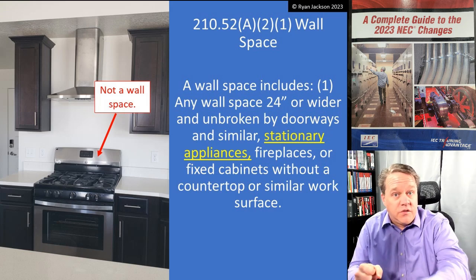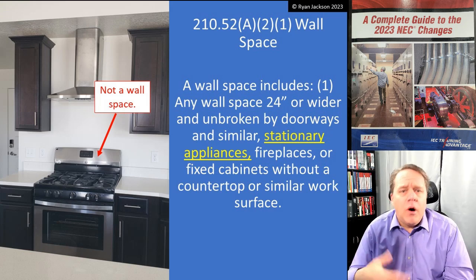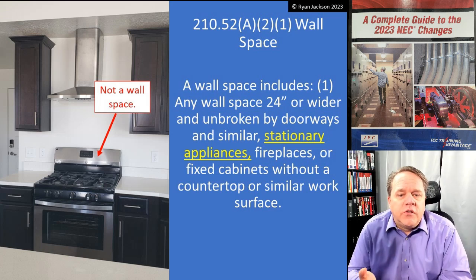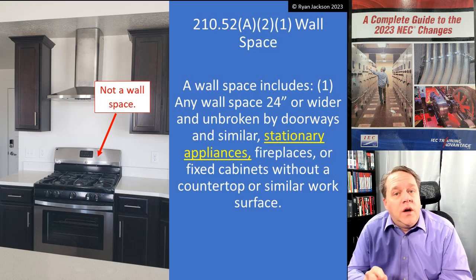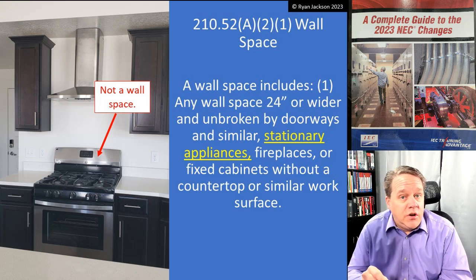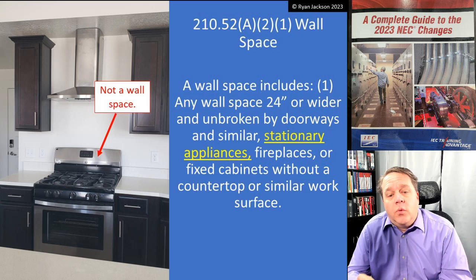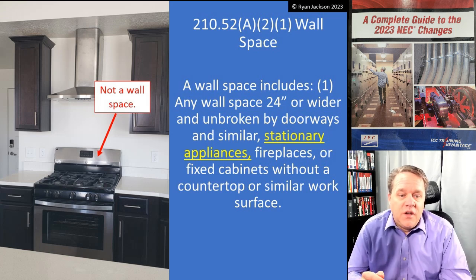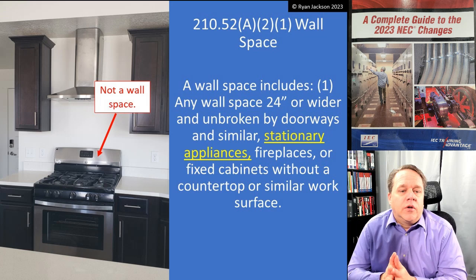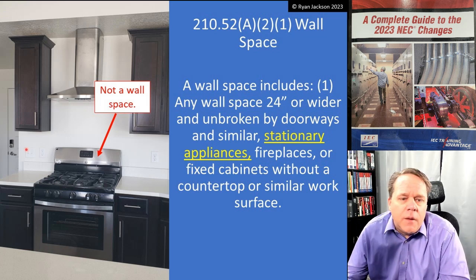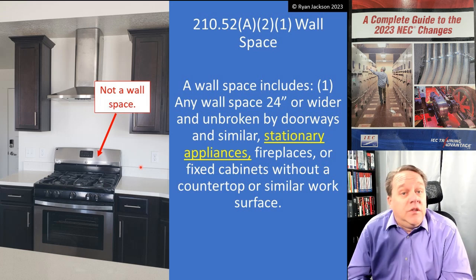The change here is in A2-1, which defines wall space. You need a receptacle for every 12 feet of wall space, reachable within 6 feet of anywhere you stand. Wall space includes any wall space 24 inches or wider, unbroken by doorways, stationary appliances, fireplaces, or fixed cabinets that don't have a countertop or work surface. In this kitchen photo, the countertops are covered by 210.52C.